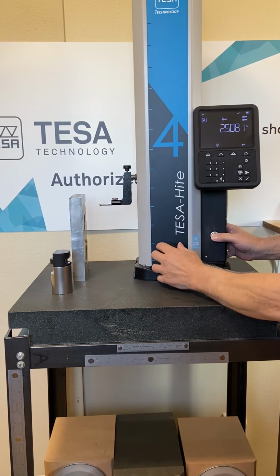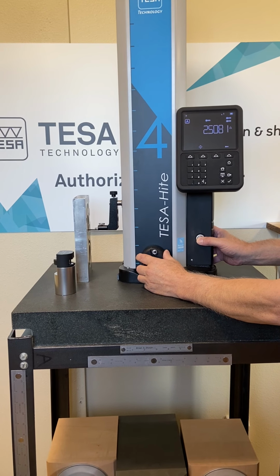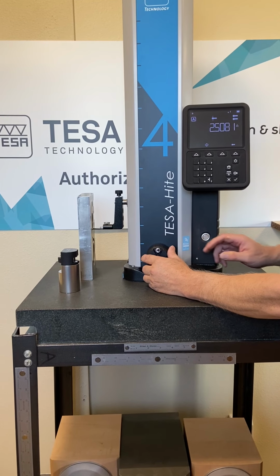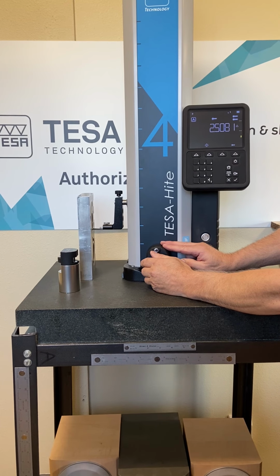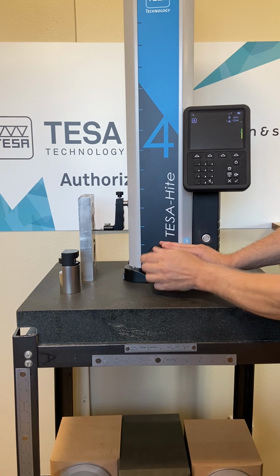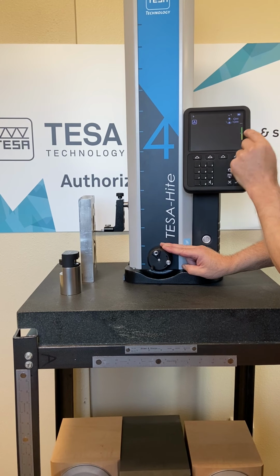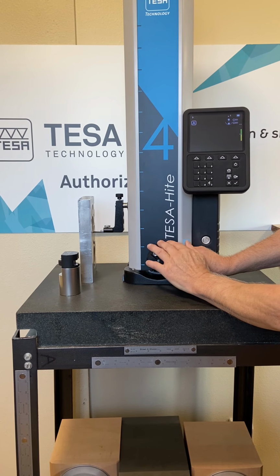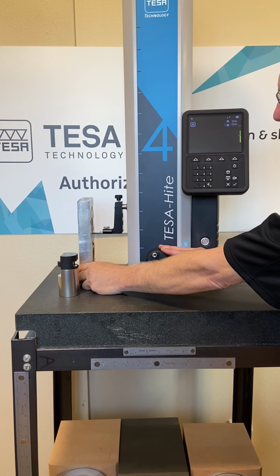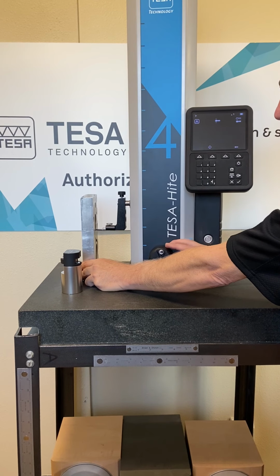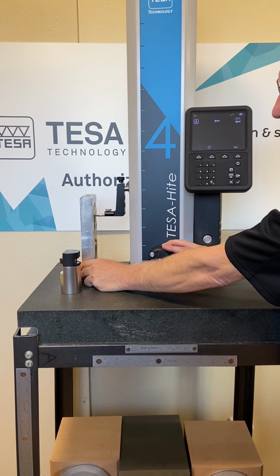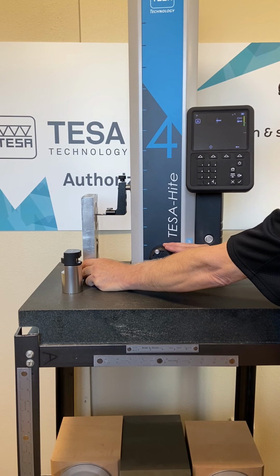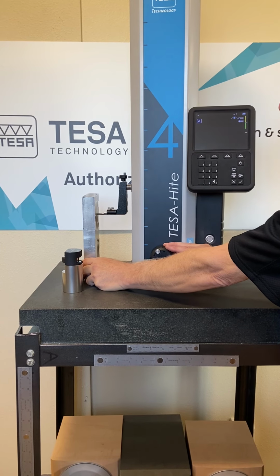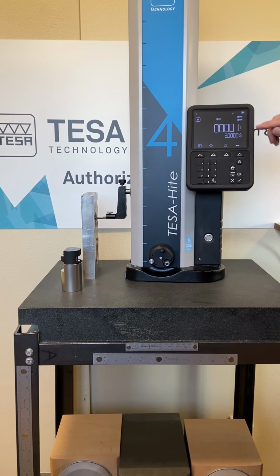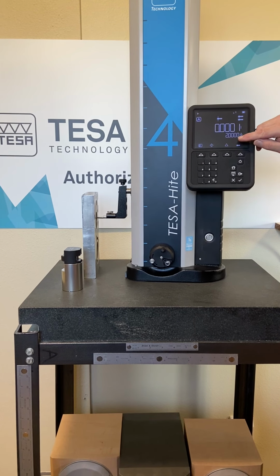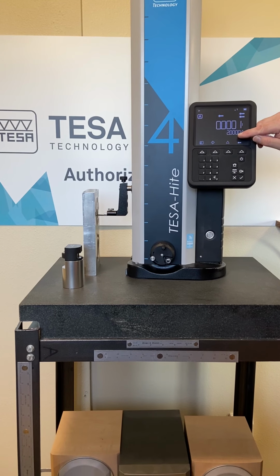If I want to do diameters, all I have to do is visually be up on the side of the bore just a little bit. So I'm going to come down here, I'm going to put pressure on the probe. These green lights want to be between those 2 lines. So now I'm just going to hold pressure on that probe as I sweep the part across. It takes the lowest point measurement. I'm going to go to the top, and I'm going to do exactly the same thing, just the opposite. It takes the highest point. So that dimension right there is center line measurement, and that dimension right there is my diameter.